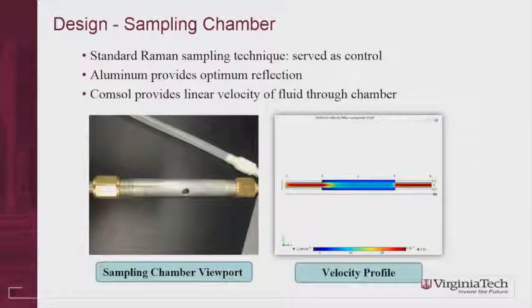So we tossed around some ideas for the sampling chamber, and we wanted to get the best sampling chamber for the best Raman accuracy. So what we chose was an aluminum tube. We chose an aluminum tube because through testing we found that aluminum had the best reflective properties for an accurate Raman scan. So right here, this is the viewport for the Raman spectrometer to take a sample.